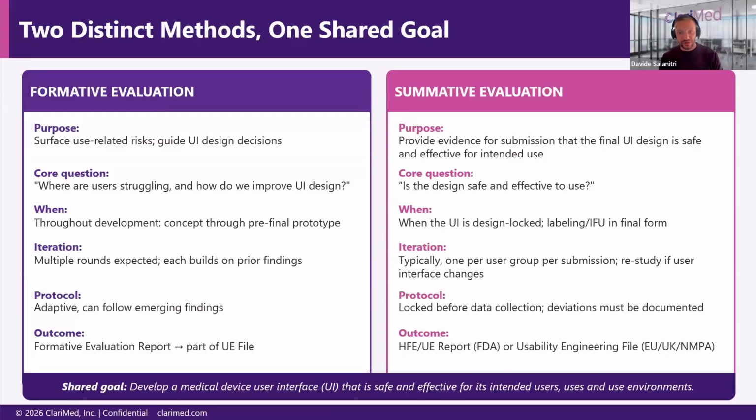The summative evaluation is what you do at the end, when your device is designed and is ready to go to market, or you think is ready to go to market. Then it is the final proof that that device is safe, is effective, and your users are going to use it without any issues causing critical harm.